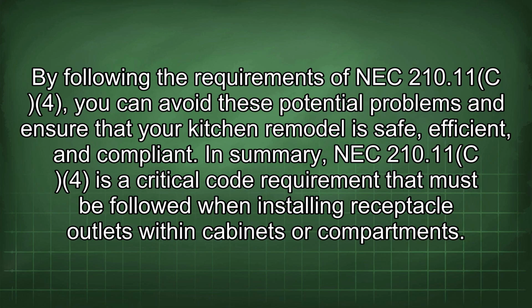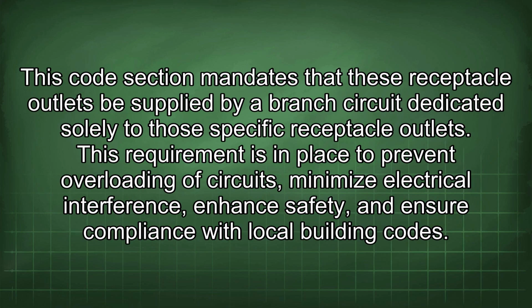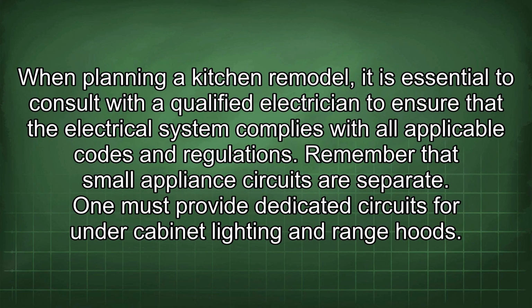In summary, NEC 210.11(C)(4) is a critical code requirement that must be followed when installing receptacle outlets within cabinets or compartments. This code section mandates that these receptacle outlets be supplied by a branch circuit dedicated solely to those specific receptacle outlets. This requirement is in place to prevent overloading of circuits, minimize electrical interference, enhance safety, and ensure compliance with local building codes. When planning a kitchen remodel, it is essential to consult with a qualified electrician to ensure that the electrical system complies with all applicable codes and regulations. Remember that small appliance circuits are separate. One must provide dedicated circuits for under-cabinet lighting and range hoods.